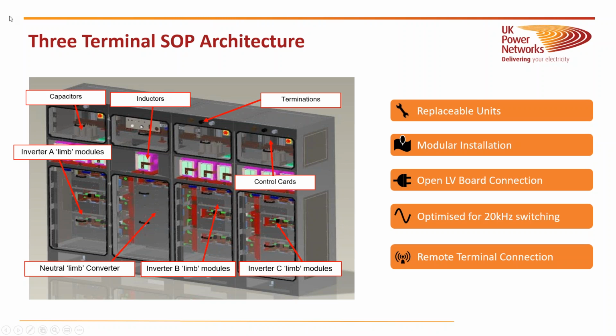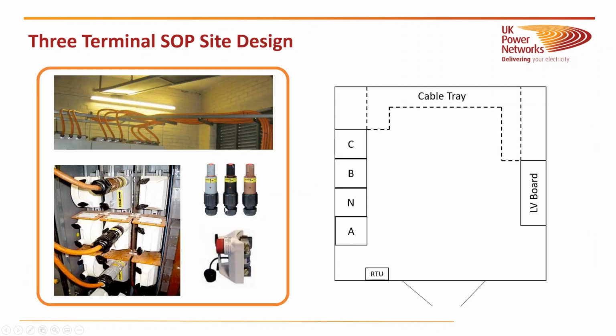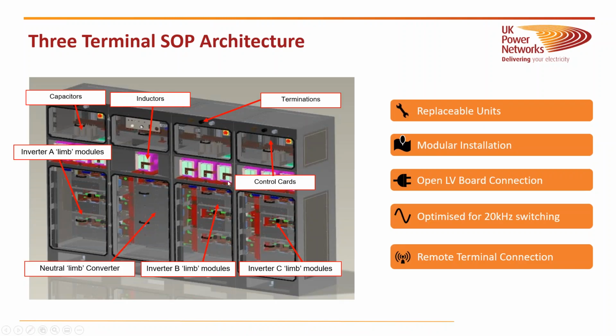Now, this is also a modular installation, because it needs to be built in an LV substation or a secondary substation. So each of these cabinets splits into 4 sections, and they can all be brought in through a door. They're designed to fit through a substation door, which makes transportation easy. An important point on the 3T SOP, which is very different to the 2T SOP, is that it needs to connect to an LV board.